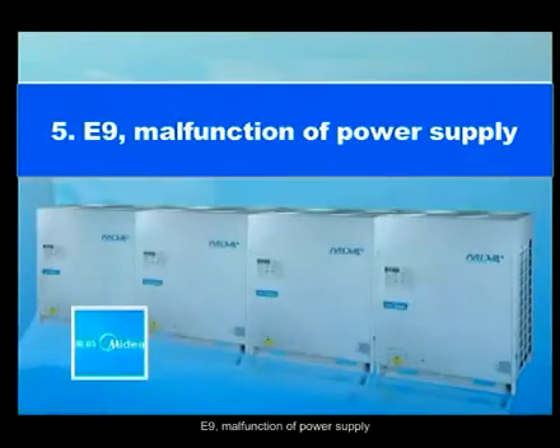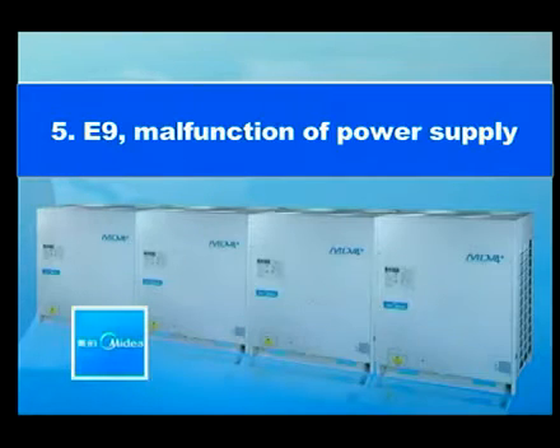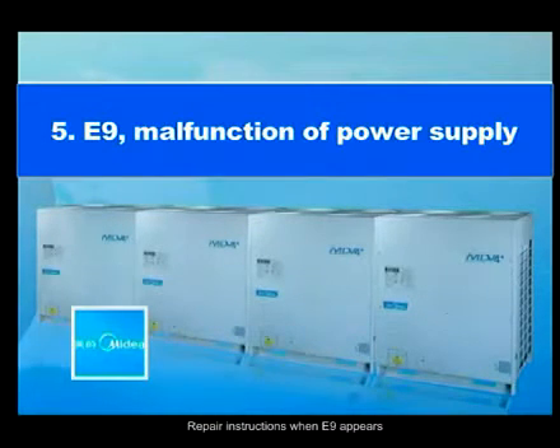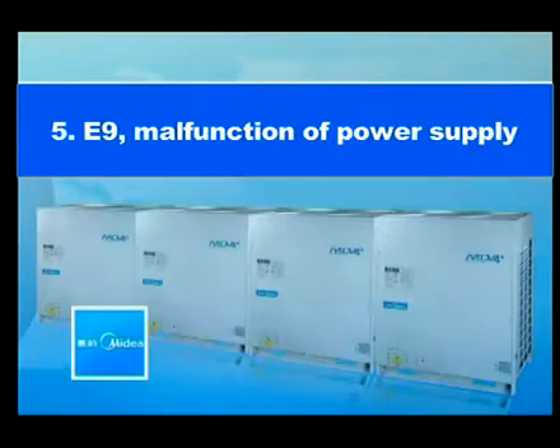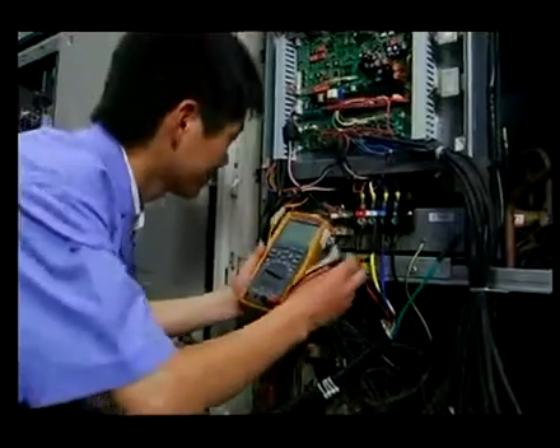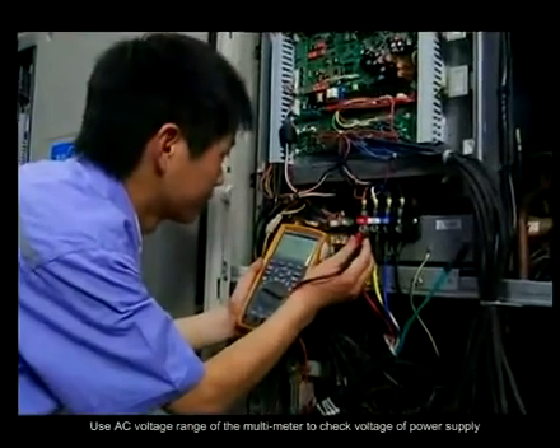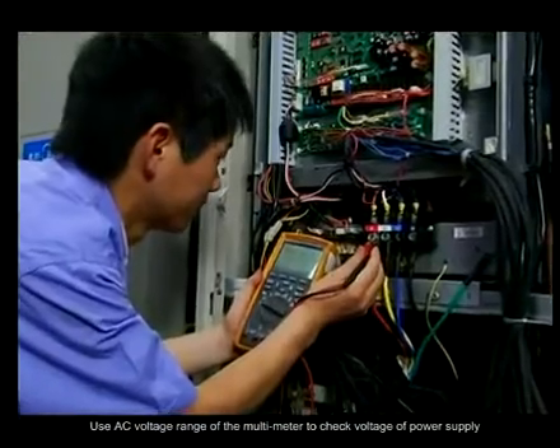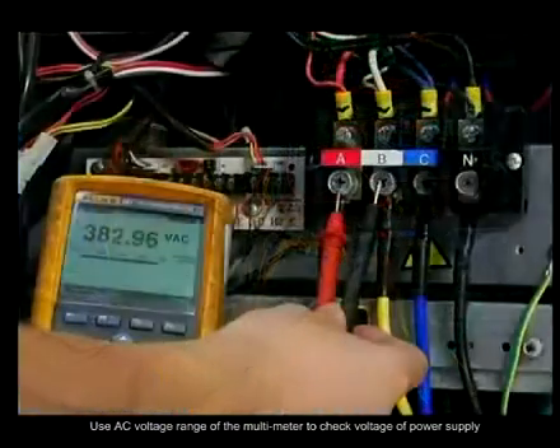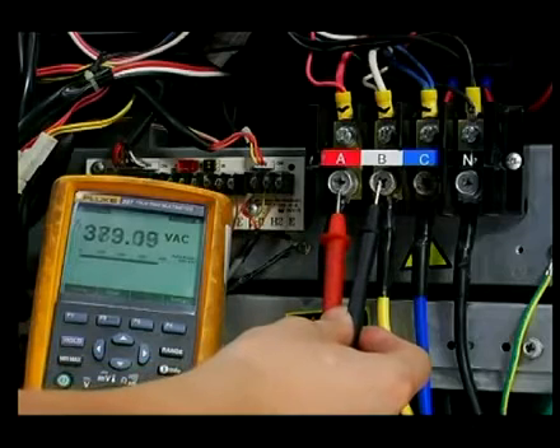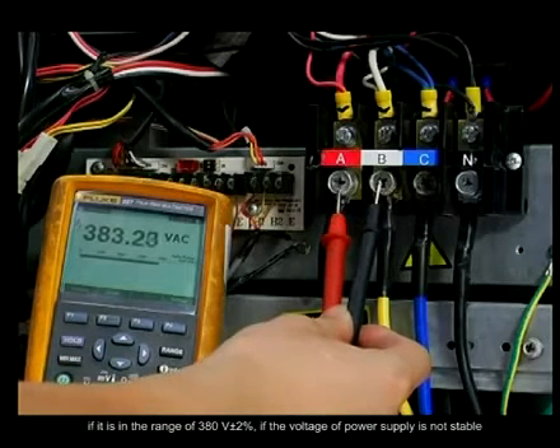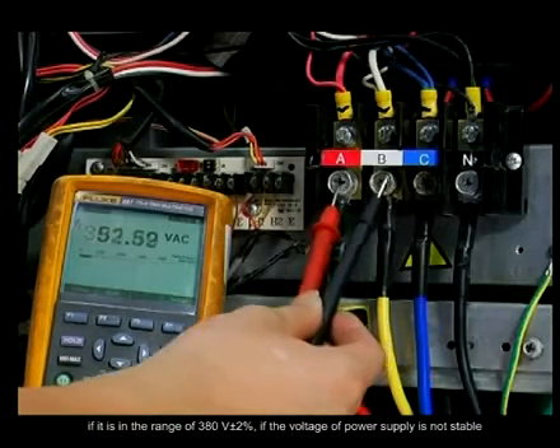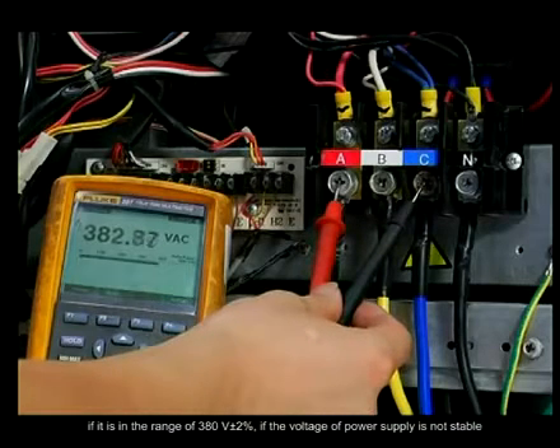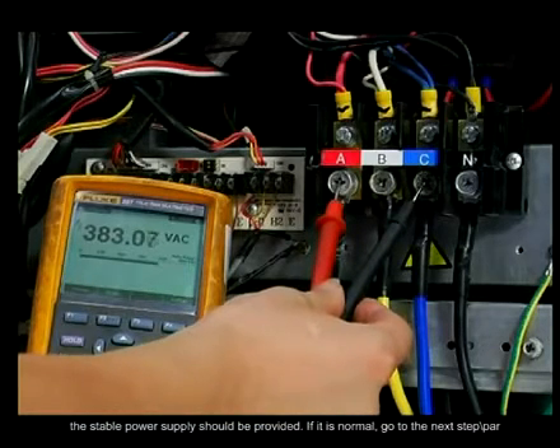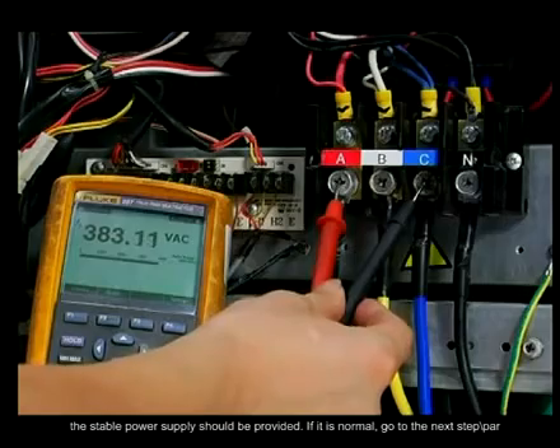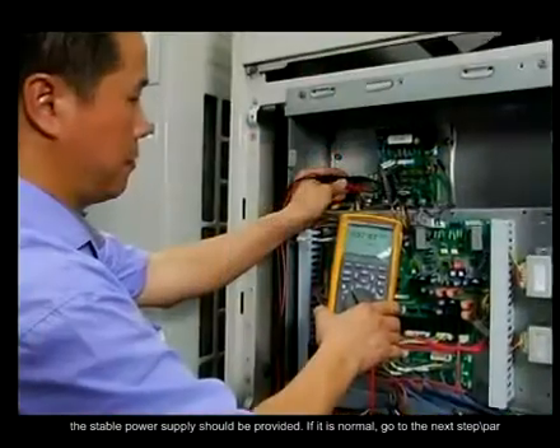E9. Malfunction of power supply. Repair instructions when E9 appears. Step 1. Use the AC voltage range of the multimeter to check if the voltage of the power supply is in the range of 380 volts plus or minus 2%. If it is not stable, a stable power supply should be provided. If it is normal, go to the next step.